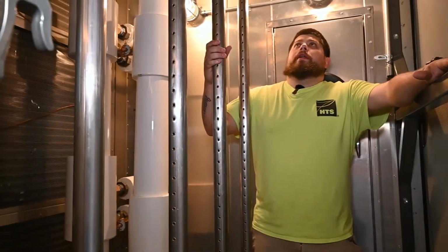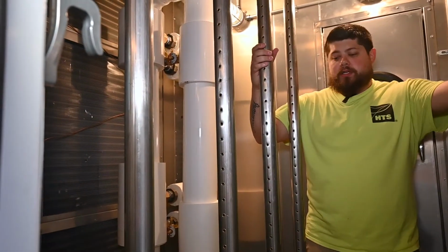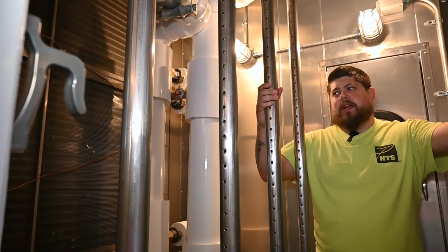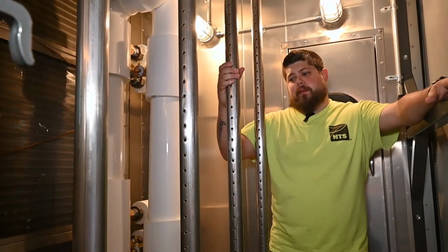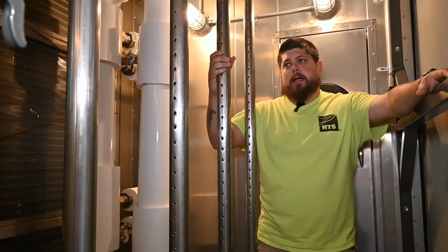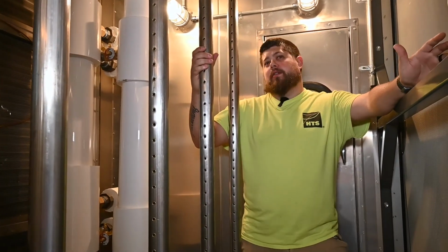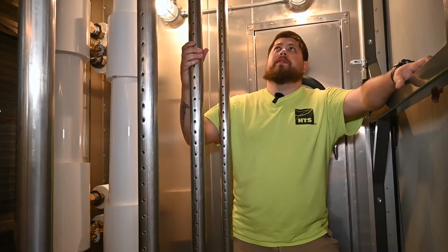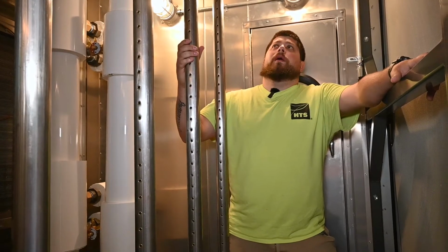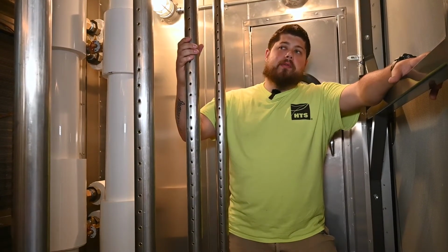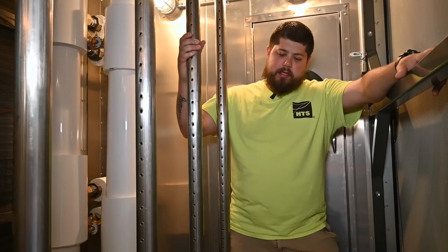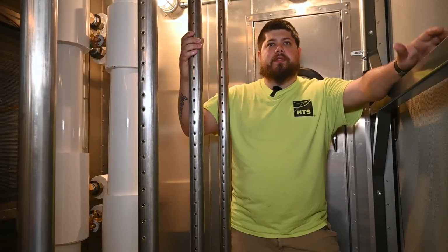This is the humidifier grid. There's not much to do with this. There's no kind of maintenance you should have to do with it. I would just periodically check it and make sure it's dispersing correctly. It is RO water, so I highly doubt you're going to see any kind of corrosion either, up to this point. If you do, way down the road, then maybe we recommend replacing parts of this grid or any of the nozzles inside. But other than that, you shouldn't have to do anything with this.